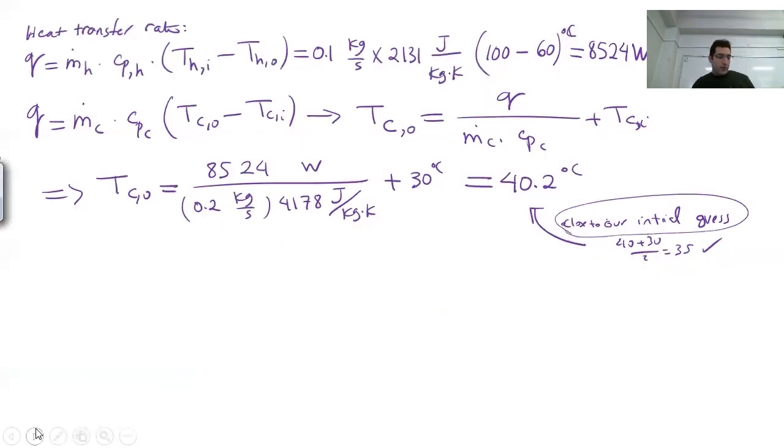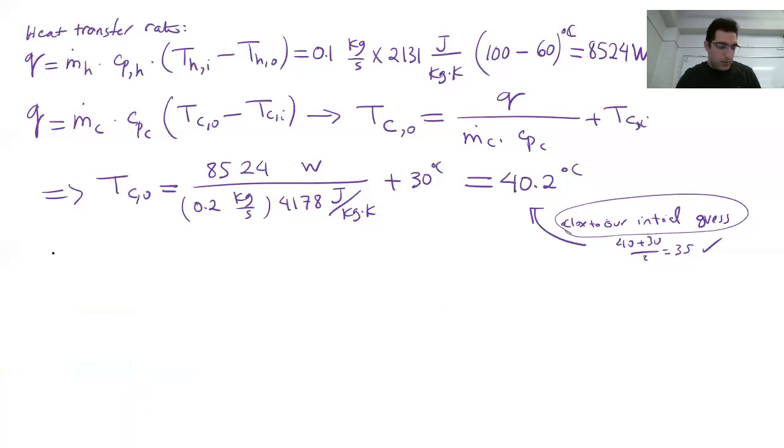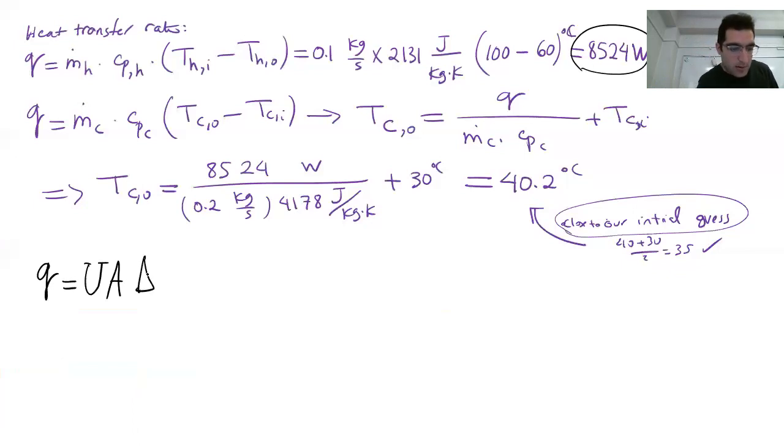Now, to solve for the length of the heat exchanger, we're going to use log mean temperature difference. So for the LMTD approach, we need to say Q, the same Q that we're talking about here, is equal to the overall heat transfer coefficient times area, the surface area between fluids, times delta T LM, the log mean temperature difference. So first of all, what is the surface area?